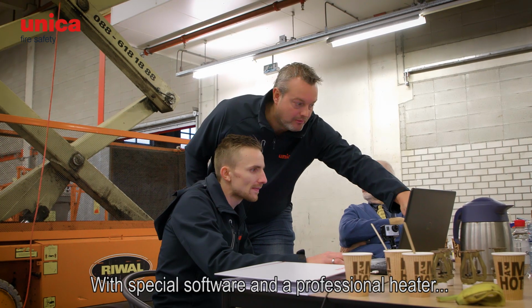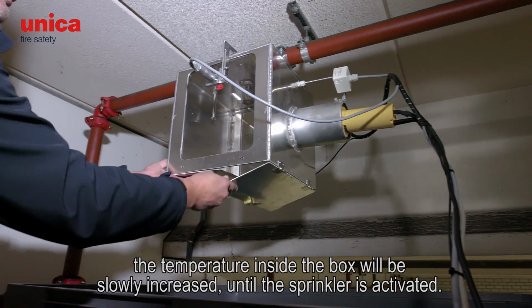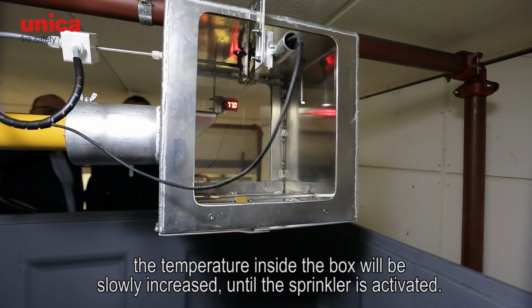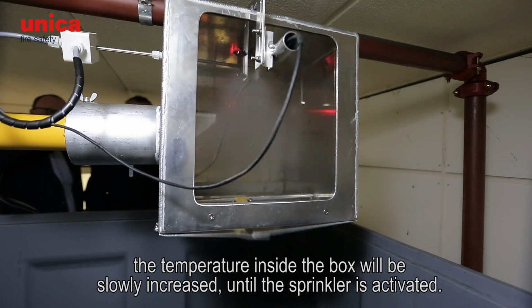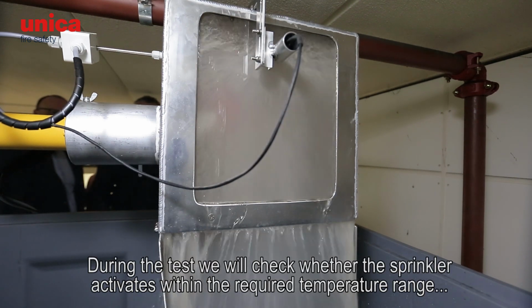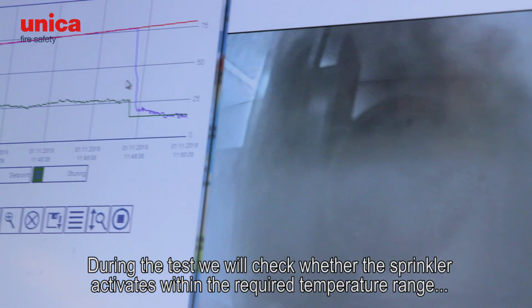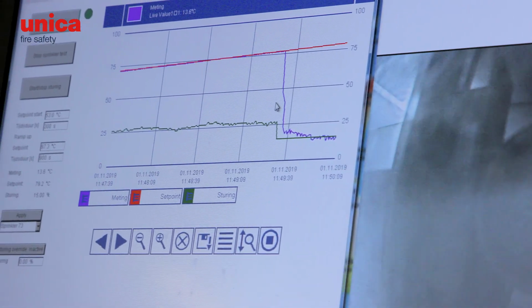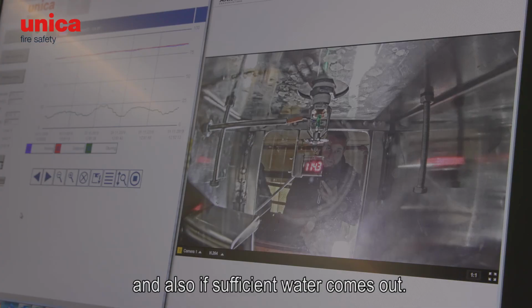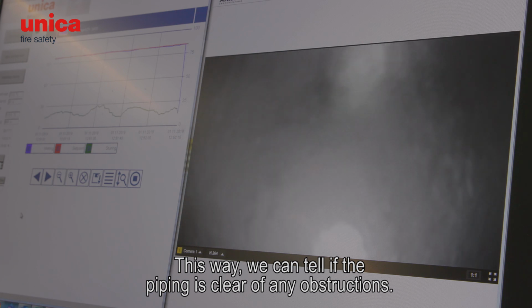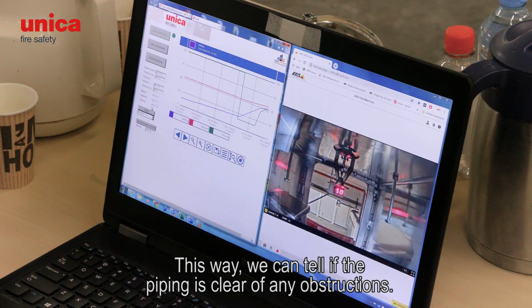With special software and a professional heater, the temperature inside the box will be slowly increased until the sprinkler is activated. During the test, we will check whether the sprinkler activates within the required temperature range, and also if sufficient water comes out. This way, we can tell if the piping is clear of any obstructions.